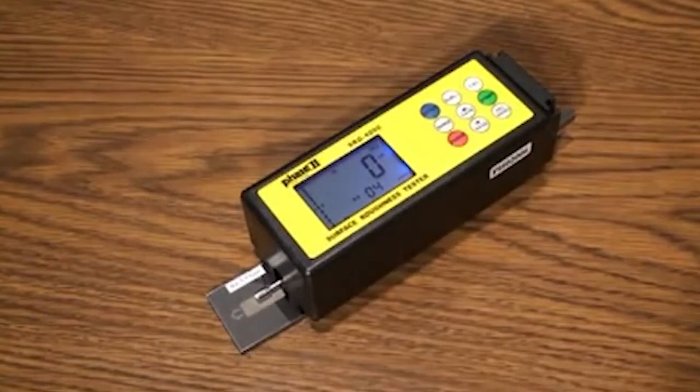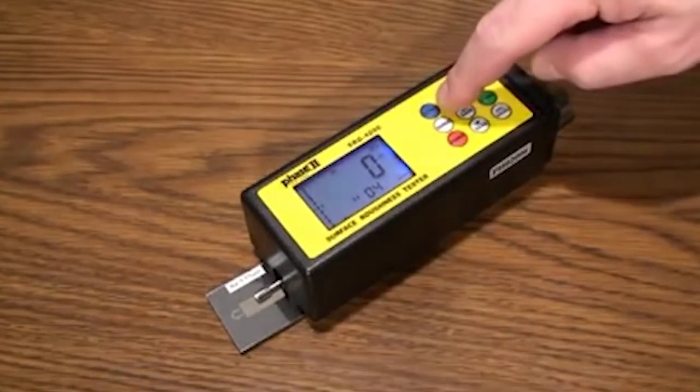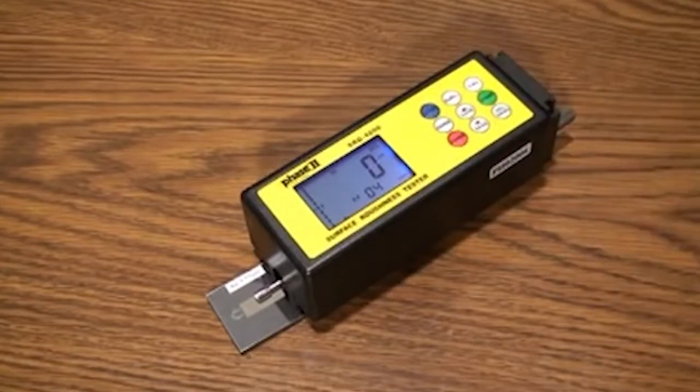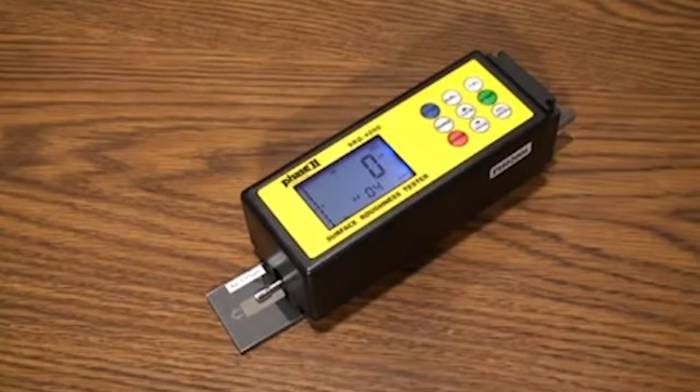The cutoff button. The cutoff length is the sampling length of the test. The correct value is determined by approximate surface roughness. This can be referenced in a chart in the operation manual showing various ranges.